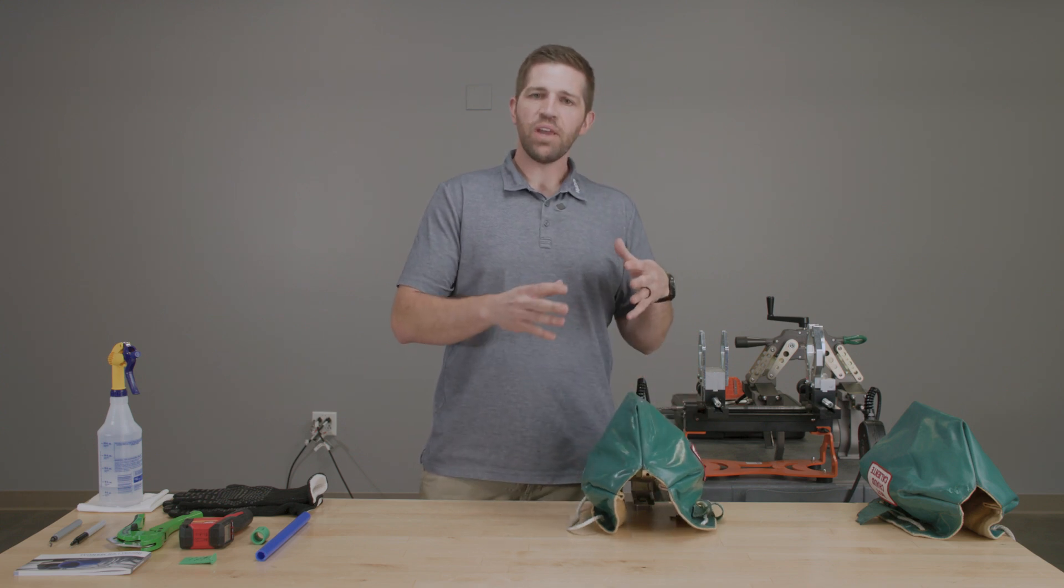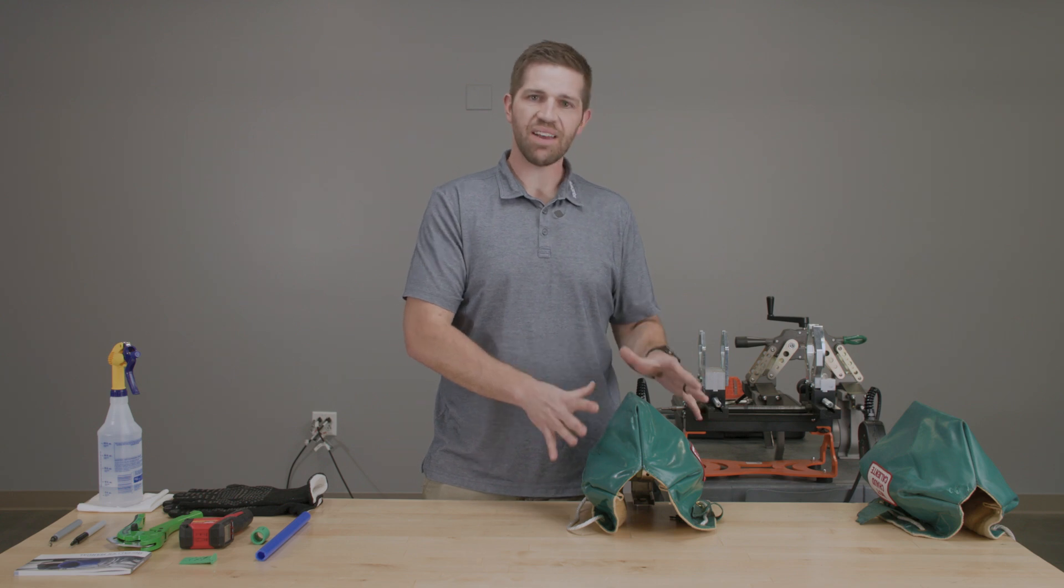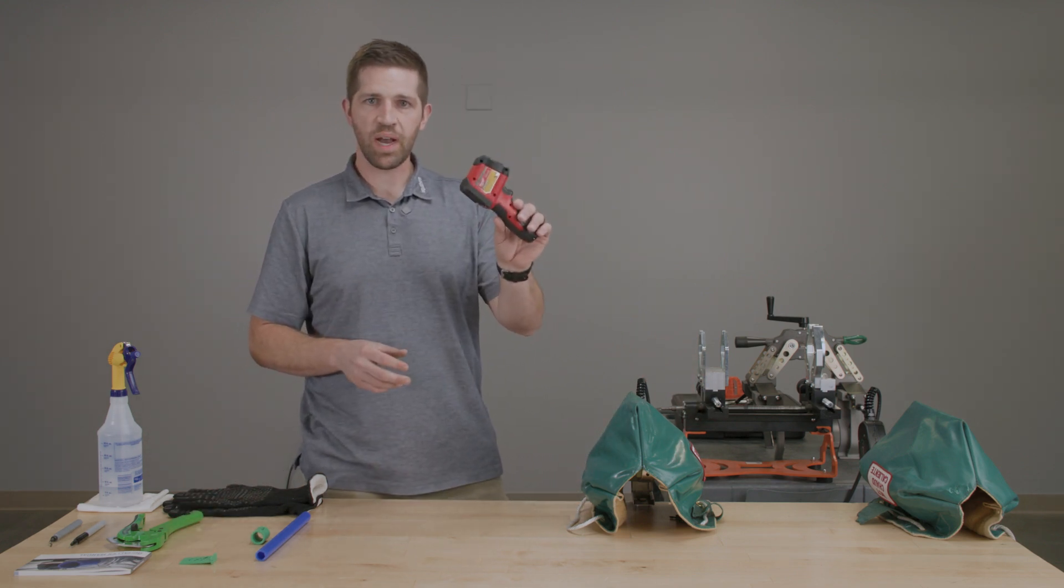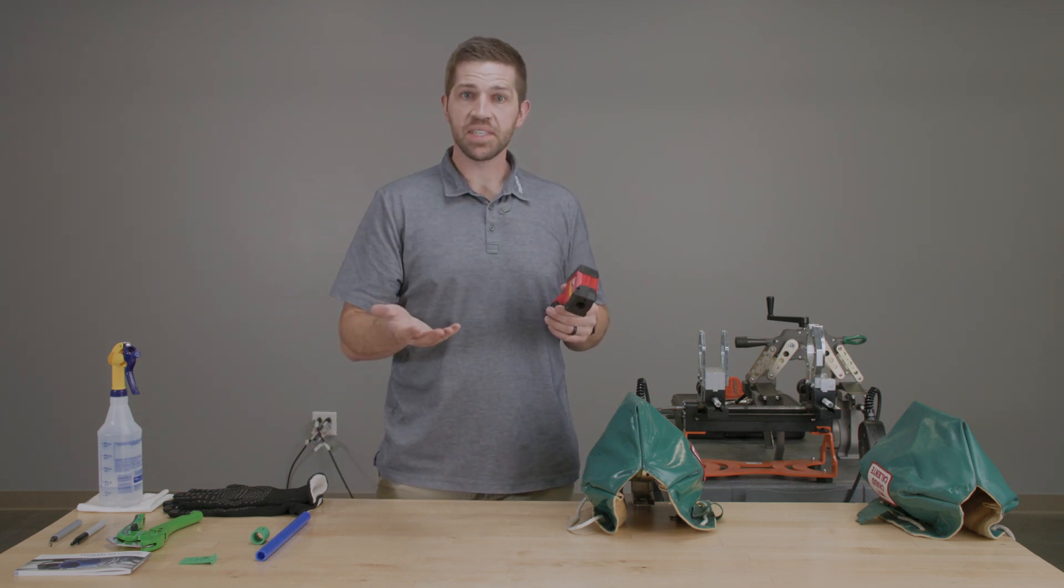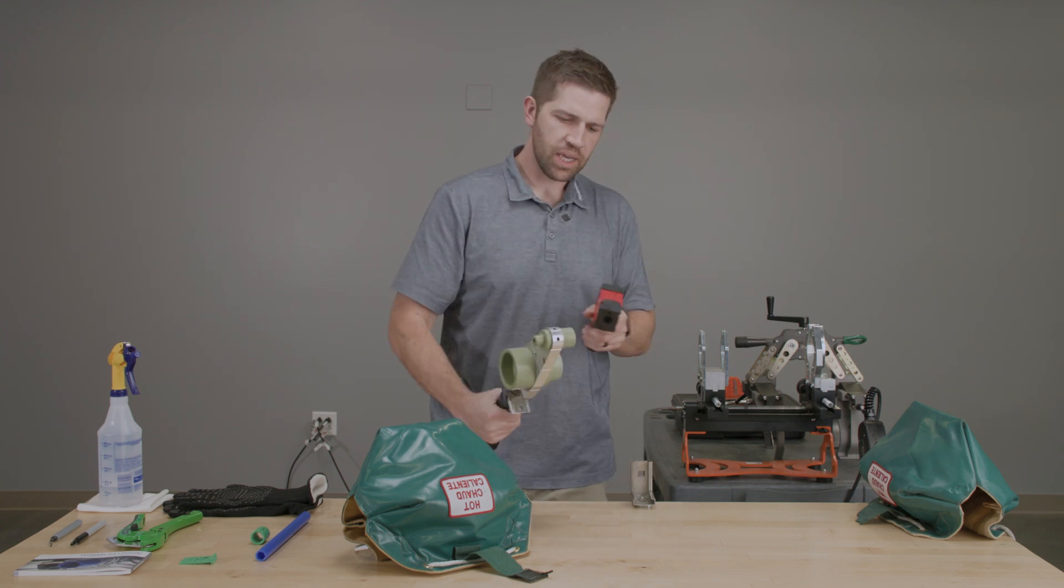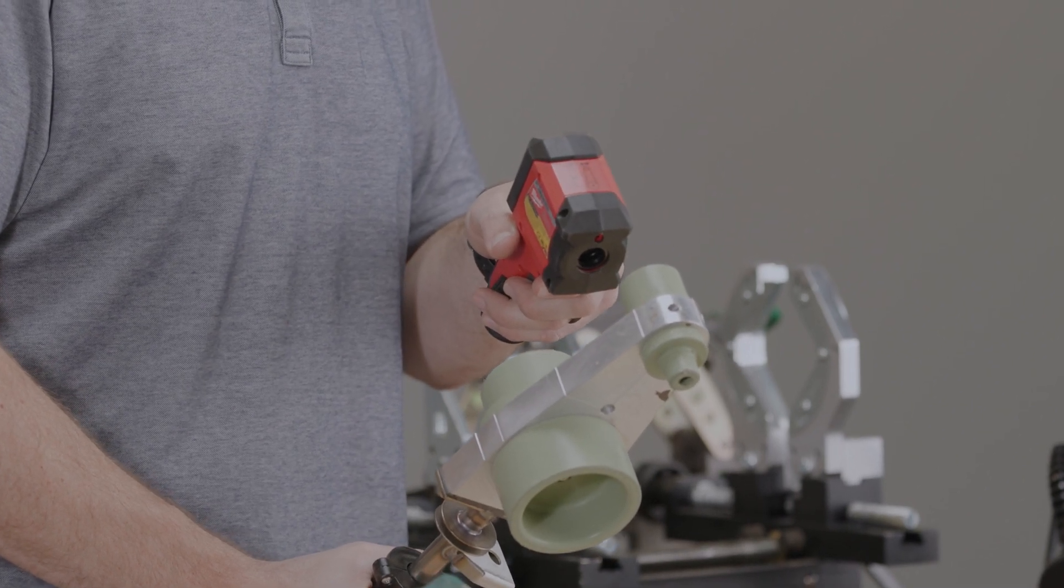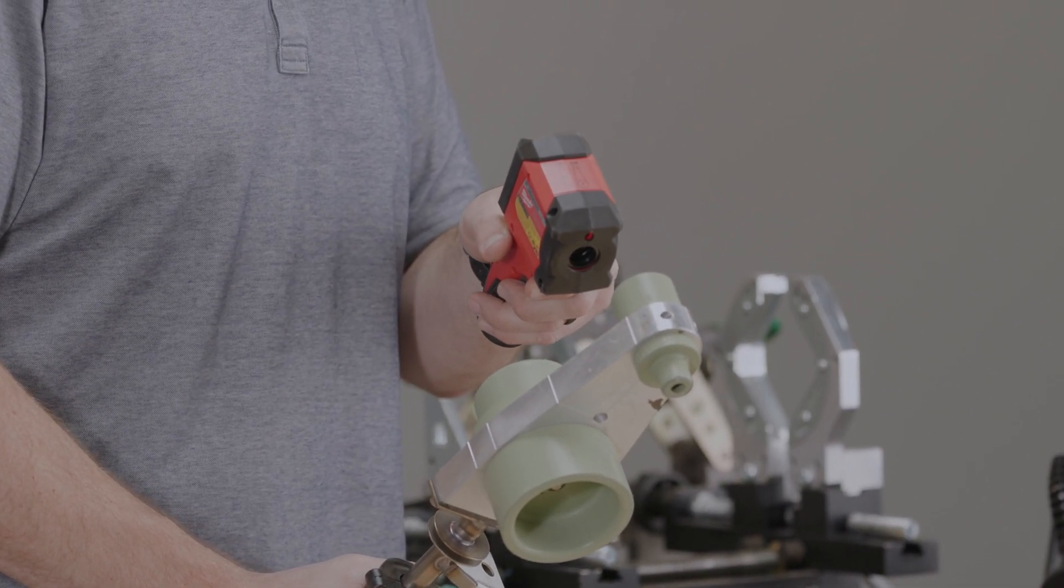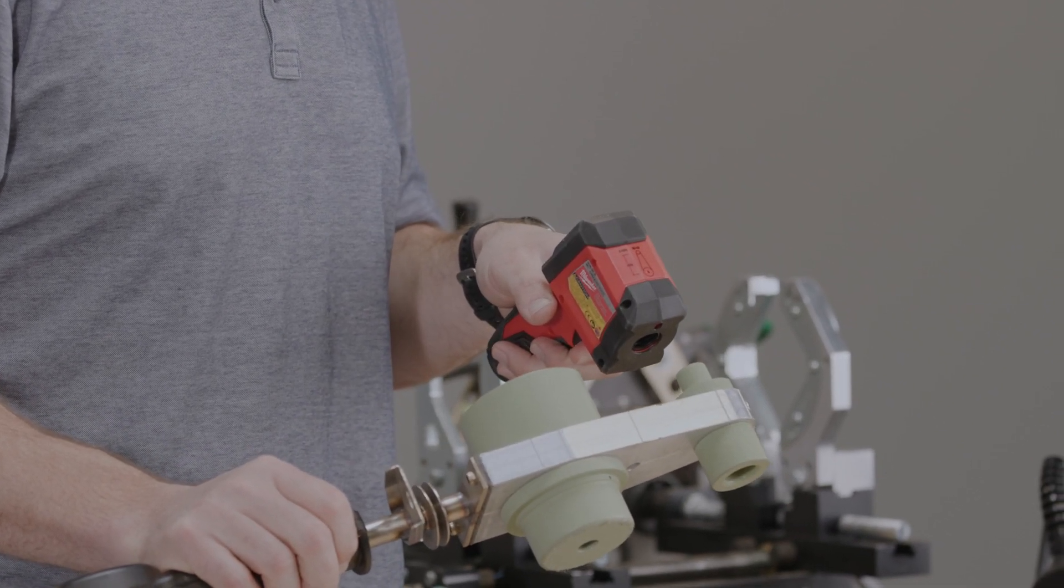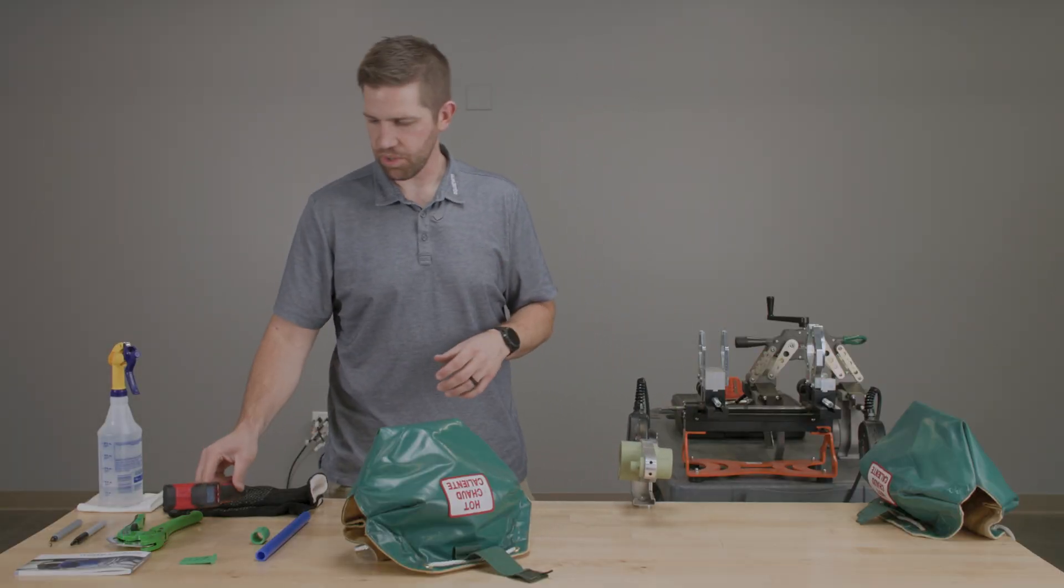When these irons are plugged in, we need to wait for them to get to the appropriate temperature. For socket fusion, that temperature should be 500 degrees plus or minus 18 degrees Fahrenheit. Make sure you have a thermometer, whether that's an infrared thermometer or a contact pyrometer, to check that temperature. I'm getting a good reading, right under 500 degrees. I'm going to check it on both sides - 497 degrees. Our irons are heated up and ready to proceed.